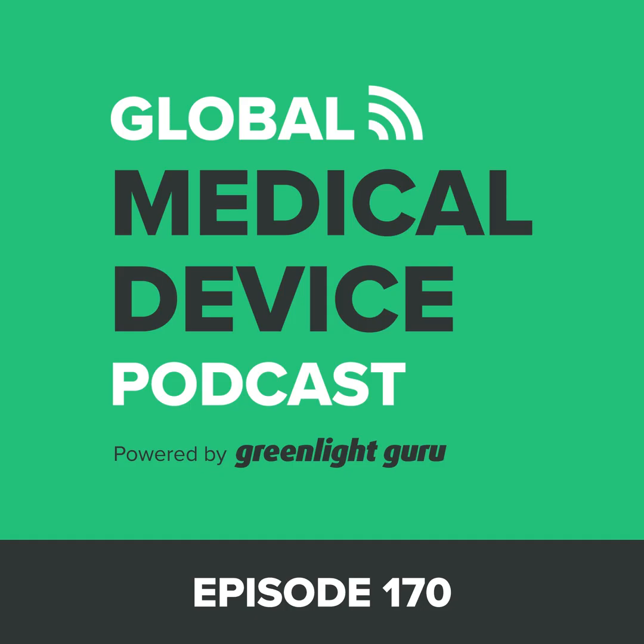Remember, folks, that a lot of times, if you put together a 510K and send it to FDA without a pre-submission, that's the first time they've ever heard of anything that you're doing. So it's all new to them, and there's probably going to be lots of questions. A pre-sub is a great way to get some of those questions surfaced a little bit earlier, so you can understand how the FDA is looking at this particular product or this space that you're pursuing. So it's a really good opportunity.